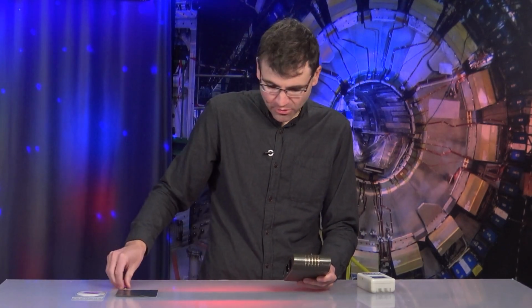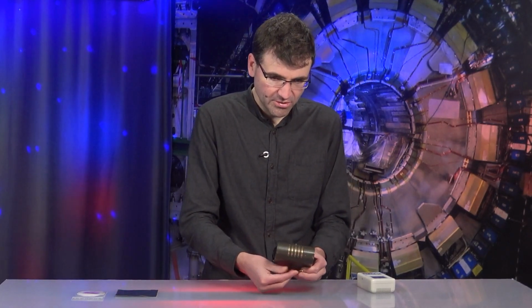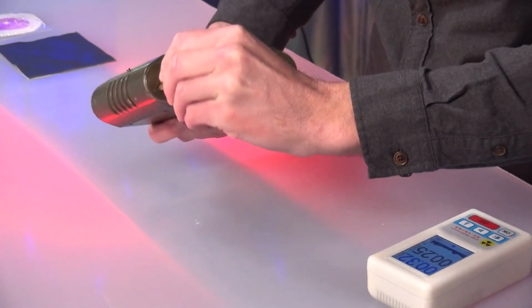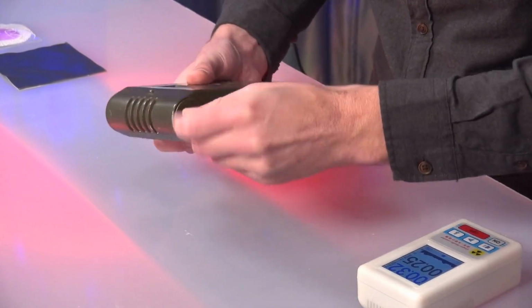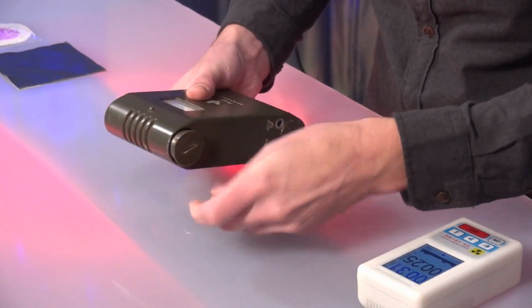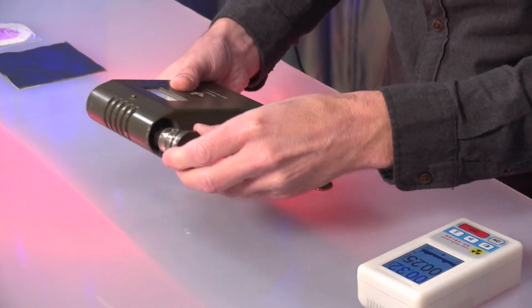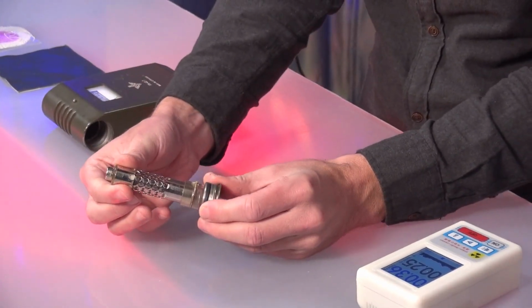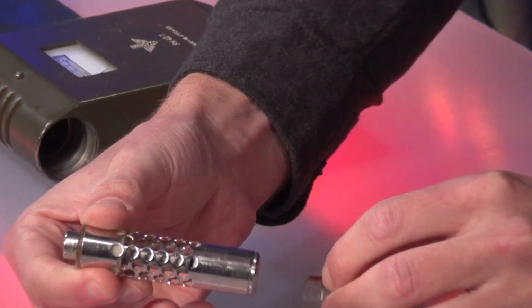How does this device do that? Well, it has a so-called Geiger-Müller counter tube built in. And if I take this counter tube out of its holder up here, it has to be unscrewed here. Then I can pull it out here. So here is the holder for the whole thing. And if I take this off here, then we have this tube.